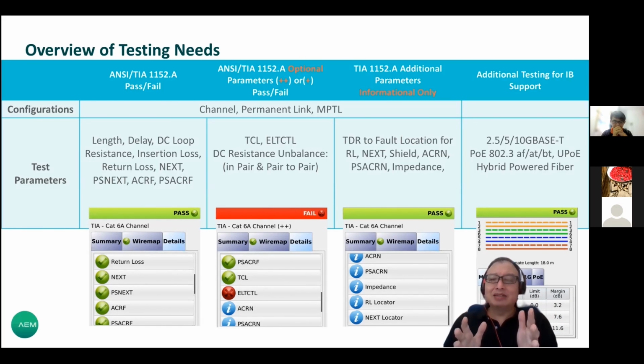In the tester, there is an option to have this parameter tested, but it will not show pass or fail. So if there's a fail in DCR or in TCL or ELTCL, it does not affect the cable certification. But we want to encourage making sure that even this additional parameter, DCR and TCL, is put to a pass and fail requirement.